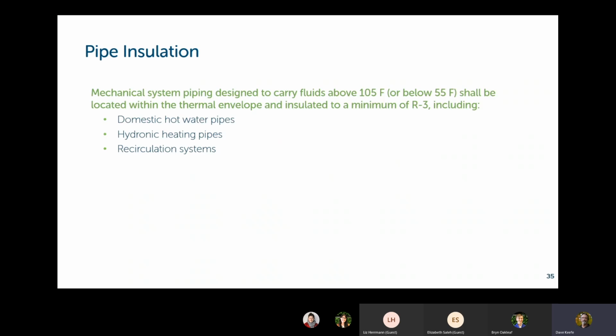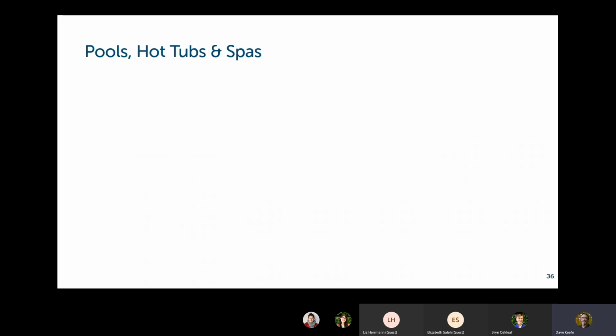Pipe insulation is required for any mechanical system piping designed to carry fluids above 105 degrees Fahrenheit. So that applies to the hot water distribution on your boiler, and it also applies to domestic hot water pipes, or at least the hot water side. There are also requirements for pools, hot tubs, and spas. If you heat your pool, the heater has to have an on-off switch. You can't have a pool heater that runs the pilot continuously.